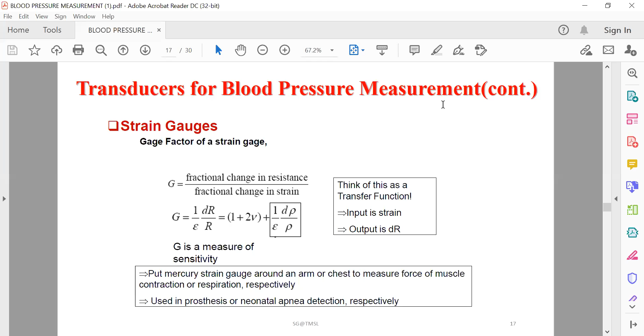The development of semiconductors that change their resistance in much the same manner as wire gauges has led to the bonded silicon element bridge. Only a small displacement of the pressure sensing diaphragm is needed for sizable changes of output voltage with low voltage excitation. Semiconductor strain gauge bridges are often temperature sensitive and have to be calibrated for baseline and true zero. Therefore, it is usually necessary to incorporate external resistors and potentiometers to balance the bridge initially as well as for periodic correction purposes. So when these strain gauges are incorporated in a pressure transducer, the sensitivity of the transducer is expressed not as a gauge factor but as a voltage change that results from a given pressure change.